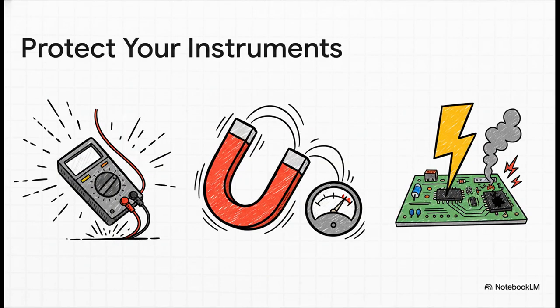So those three dangers are, number one, mechanical shock. Pretty simple. Dropping or even just bumping a meter can knock its sensitive internal parts out of alignment. Number two is strong magnetic fields. Getting a meter too close to a strong magnet can permanently mess up its accuracy. And number three, excessive current. Trying to measure too much current can literally overload and fry the meter's circuits. That's why you always start on the highest range and work your way down.